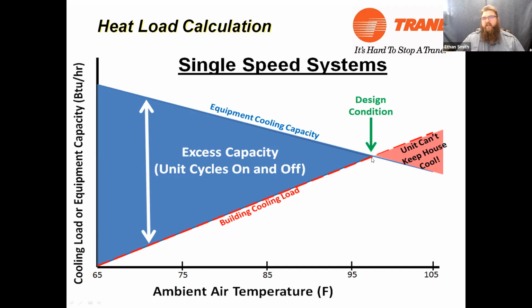Above that design condition, we can't cool the house. Below that design condition, anytime we're not right at design condition on a single stage piece of equipment, we end up having excess capacity. This is pretty familiar to everybody, but that's kind of the double-edged sword. We've got to make sure that we can keep them cool on the hottest day of the year, and we've got to make sure that we have enough equipment. So this takes care of our sizing issue. However, this is not terribly friendly to zoning because this is the entire house's load. So if we're going to break up that load into zones, is a single stage piece of equipment always going to work for us?